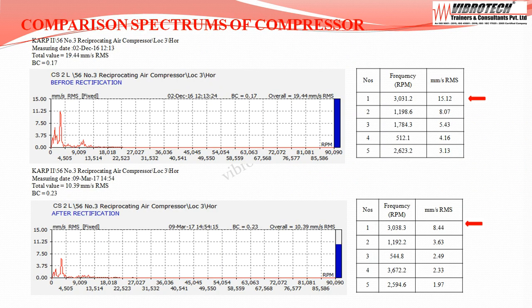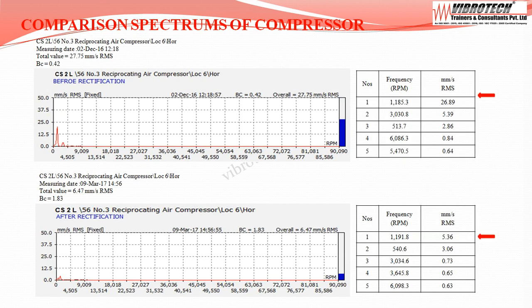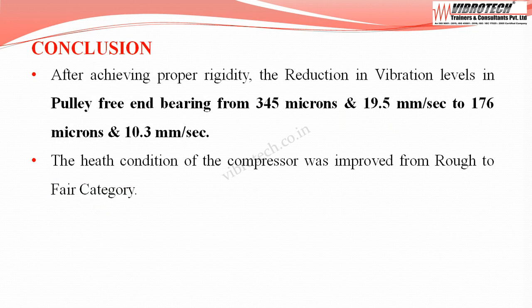Going through the comparison spectrum at pulley free end bearing, a reduction in overall vibration levels from 345 microns peak to peak was observed. At the low pressure cylinder, reduction in overall vibration from 27.75 mm/s rms to 6.47 mm/s rms was achieved. After achieving proper rigidity, the reduction in vibration levels at pulley free end bearing went from 345 microns peak to peak and 19.5 mm/s rms, down to 176 microns peak to peak and 10.3 mm/s rms. The health condition of the compressor improved from rough to fair category.